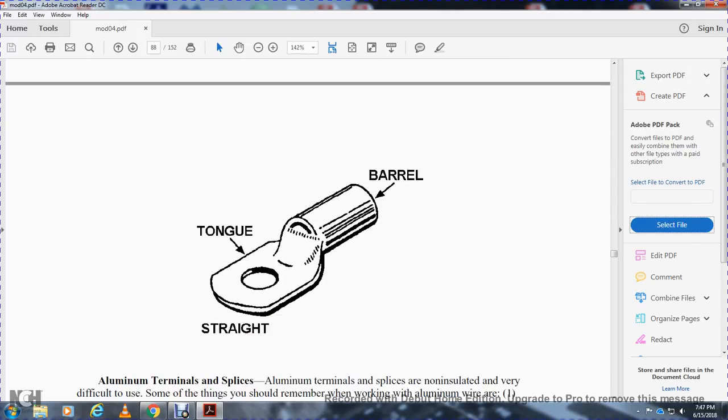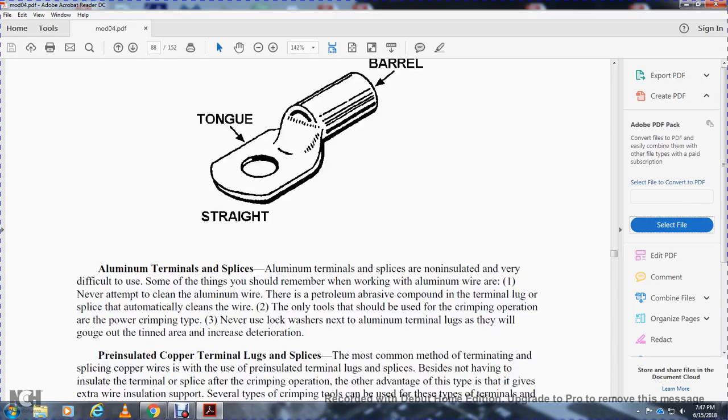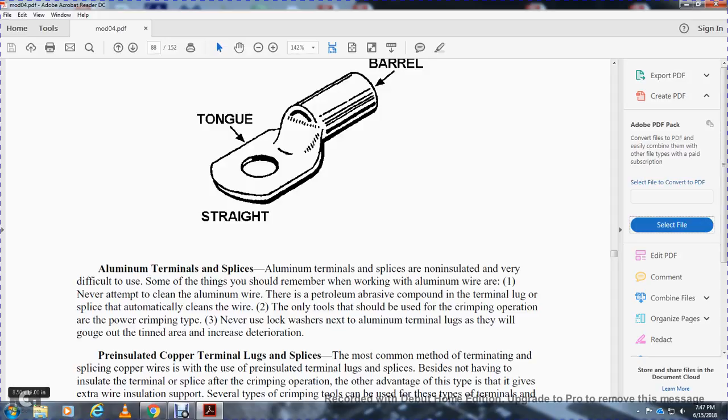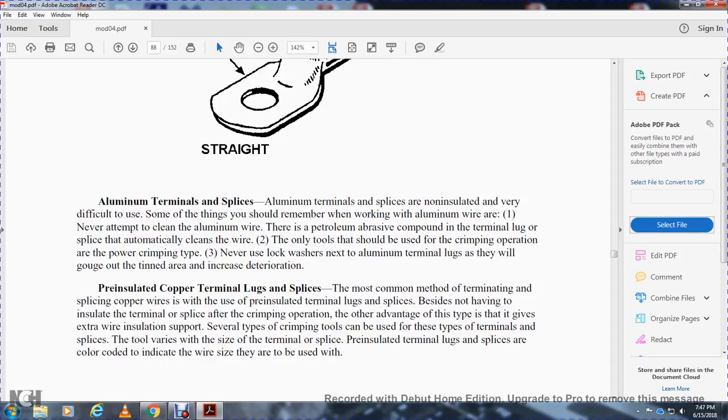This shows the barrel tongue variety, the aluminum terminal splice. Aluminum terminal splices are not insulated and very difficult to use. Some things to remember when working with aluminum wire: never attempt to clean aluminum wire. Use a petroleum abrasive compound with the terminal lug splice that will automatically clean the wire. The only tools that should be used for terminal crimping operations are power crimping tools. Never use a lock washer next to the aluminum terminal lugs, as they will gouge out and tend to corrode with increasing deterioration.